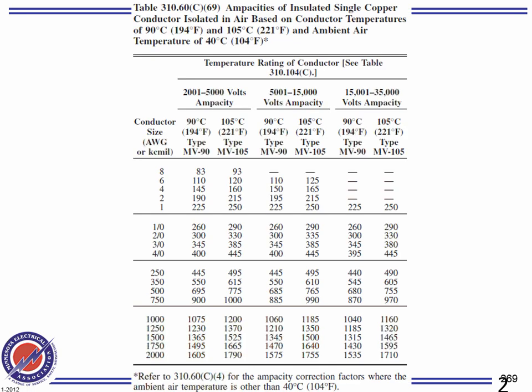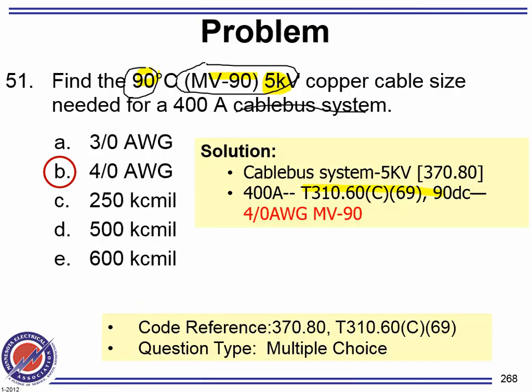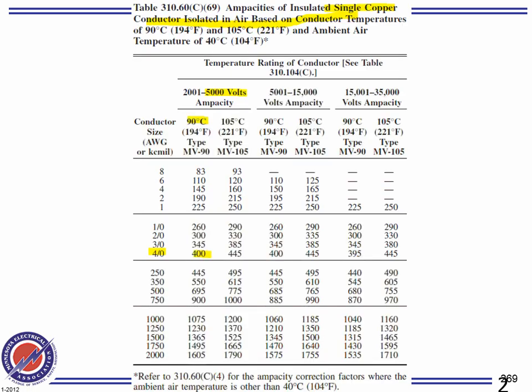Okay, here's the table. It says ampacity of insulated single copper conductor in the air. Voltage limit 5K. Temperature 90. And what was the current that we're carrying? 400. And then you're going to go all the way to 400, and that'll get you what? 4 out. They'll get you 4 out.